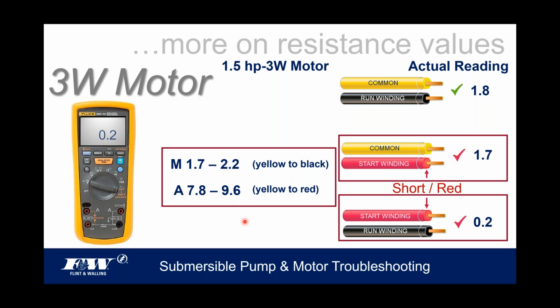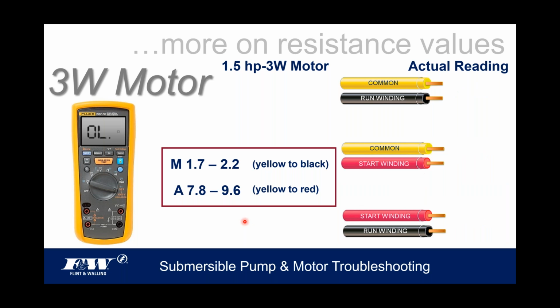Okay, moving to the next one here. We're going to do another test. Now this time, I put my probes on my yellow and black, and I end up with 8 ohms. Well, that's not within range. In this case, it's coming in higher than specified. So I come down to the next one, yellow and red, and that's coming in at 9.4. Well, hey, that's right within range. So I failed on the top one this time, and I come in higher.